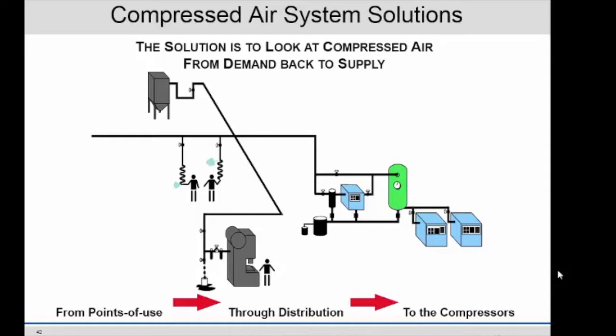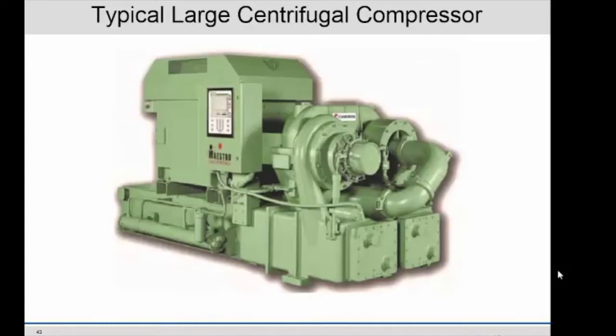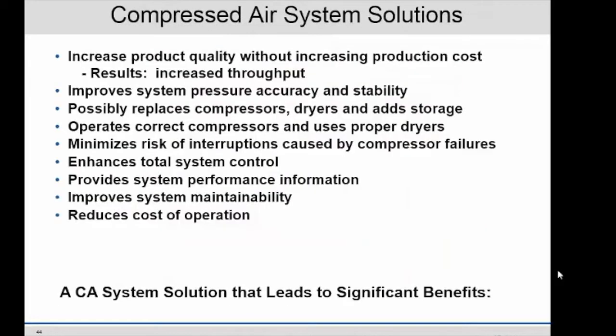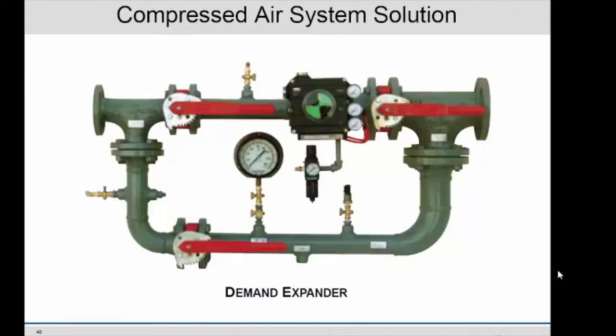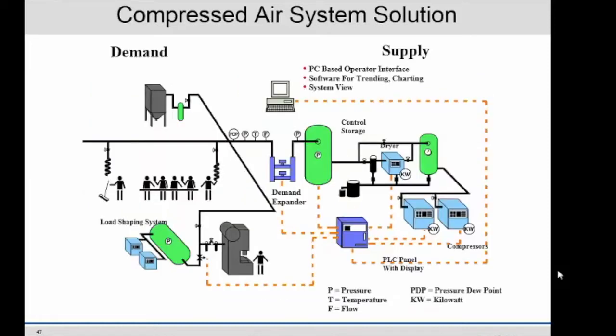Very wasteful. So what we do is we automate it a little bit more. We put in a more efficient compressor that can load and unload. I don't have time to go over all of that. But we also put in this expander station. And this expander station is kind of the brains, where you separate the system from the compressors. So you operate your compressors as efficiently as you can. You have more storage usually, because you probably need more storage for it not to dump that air in the alleyway. Okay? And then you maintain constant pressure going out to the people using the air. So it's whatever air pressure you need. It's not going to cycle between 100 and 125. It's whatever you need to be out there. It could be 60 psi. So you operate much more efficiently with that expander station separating the two.